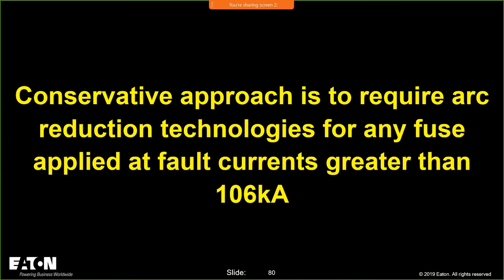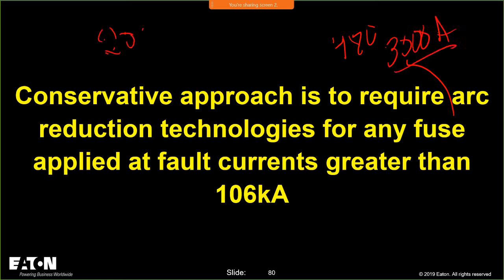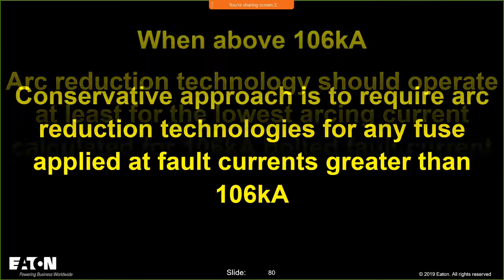Again, the conservative approach is to require arc reduction technology for any fuse applied at fault currents greater than a certain level: for a 480 volt system, 3,000 amps and greater. For a 208 volt system, it's around, I think, 1,600 amps. I can't remember. But like I said, if I had a 2,000 amp fuse and I had 180,000 amps, I can show you that I don't necessarily need to employ a technology because that arcing current is going to trip fast.